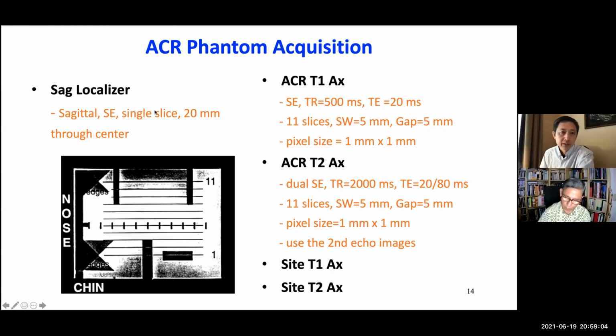So for weekly testing, we only do 2 scans, the sagittal localizer and the ACR T1. For annual testing, we do 3 scans: sagittal localizer, ACR T1, and ACR T2, okay? If the site is applying for ACR accreditation, then 2 additional scans will be required, which are site T1 and site T2. So basically we use a site protocol to scan the ACR phantom.